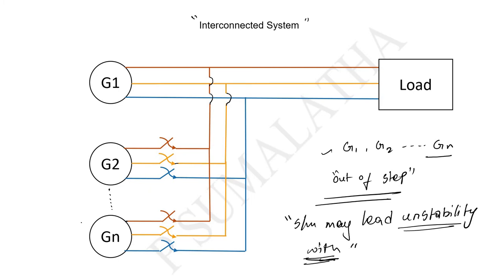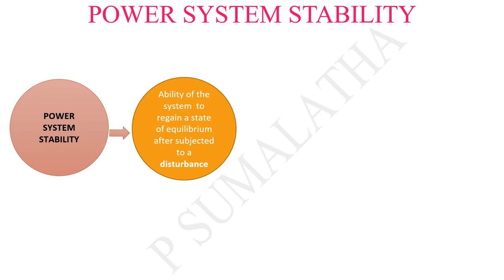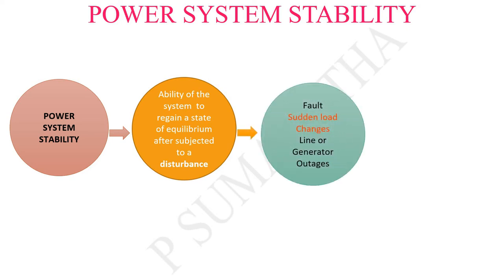Therefore the power system stability has been restated as the ability of the system to regain a balanced condition after being subjected to a disturbance. Once the system is subjected to a fault, if it is able to come back to normal condition then the system is under stable condition. A disturbance is nothing but a fault, a sudden load change, or the tripping or outages of transmission lines or generators. These disturbances are categorized into two different types in stability studies: large disturbances and small disturbances.